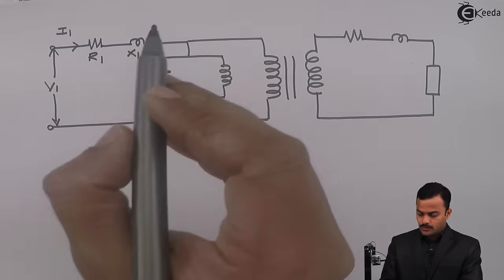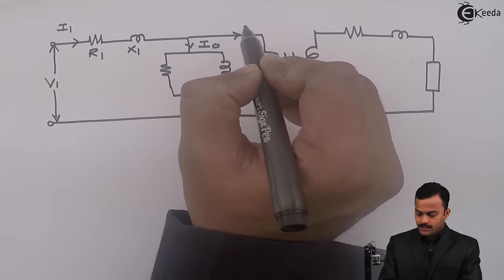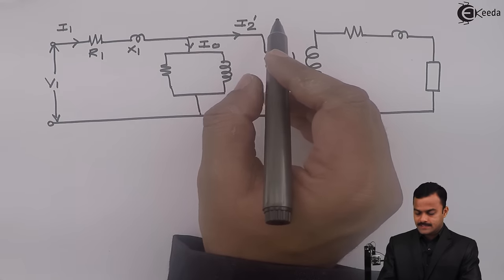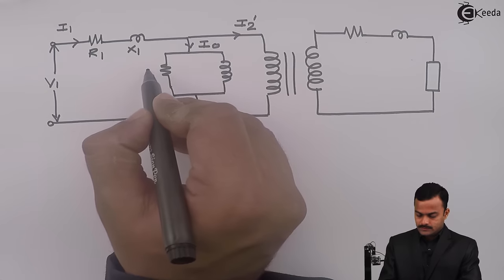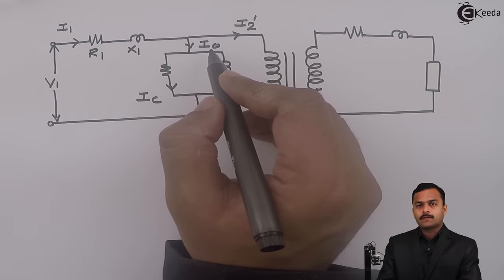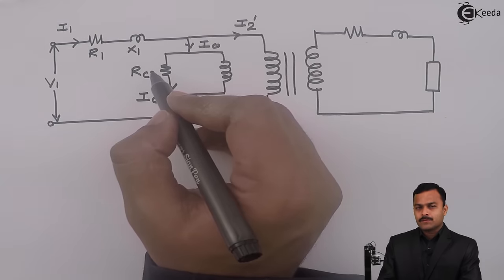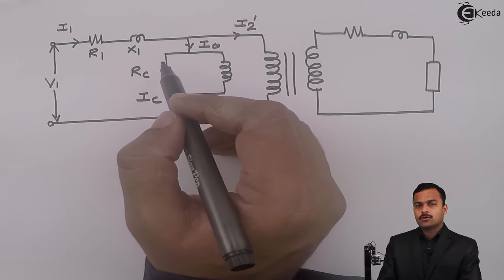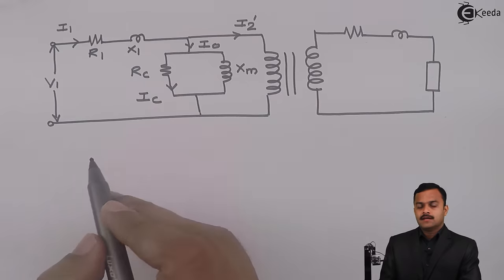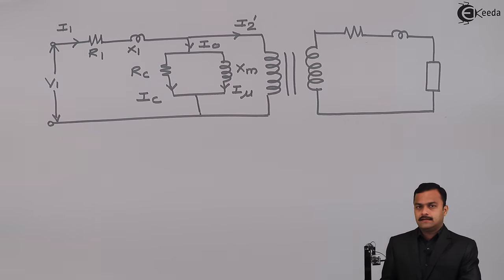This I1 has two components: the no-load primary current, which is denoted as I0, and the current which is responsible for nullifying the effect of Phi2, which we call I2 dash. This I0 also has two components. One flows through the core loss resistance RC, which is called the core loss component of no-load primary current and represents how much core loss is happening inside the core. The other flows through XM, the magnetizing reactance, and this current is Imu, the magnetizing component of no-load primary current I0.